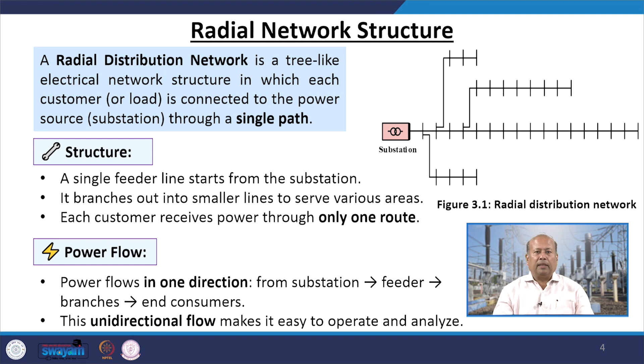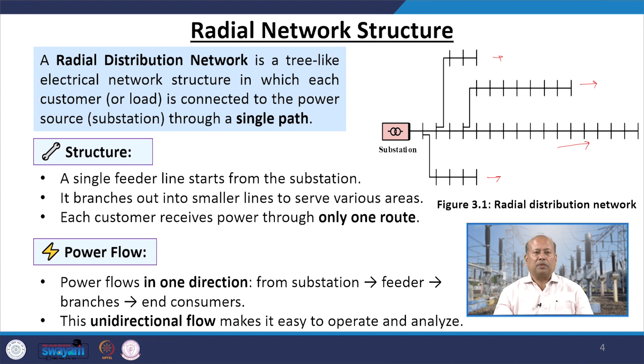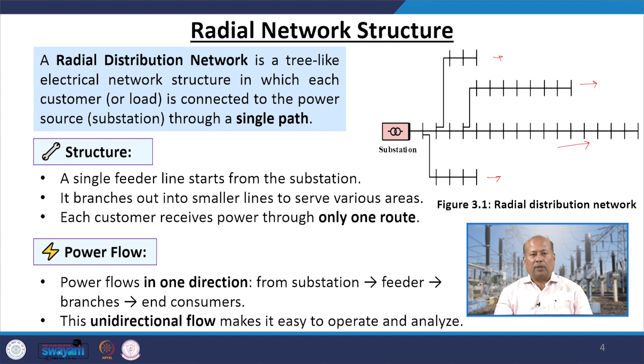A radial distribution network is a tree-like electrical network structure in which each customer or load is connected to the power source substation through a single path — there is no closed path. A single feeder line starts from the substation and branches out into smaller lines to serve various areas, and each customer receives power through only one route. Power flows in one direction from substation to feeder to branches and end consumers — this is known as unidirectional flow of current — and it is quite easy to operate and analyze.